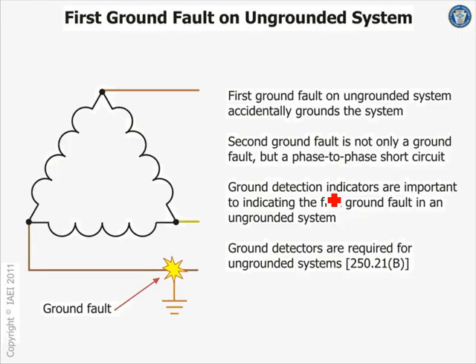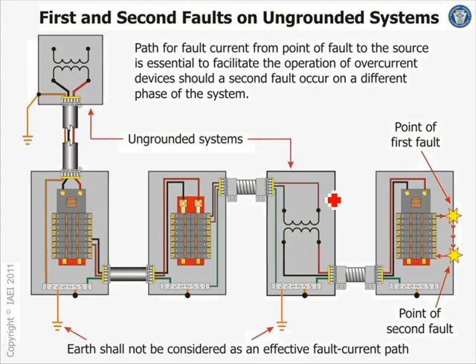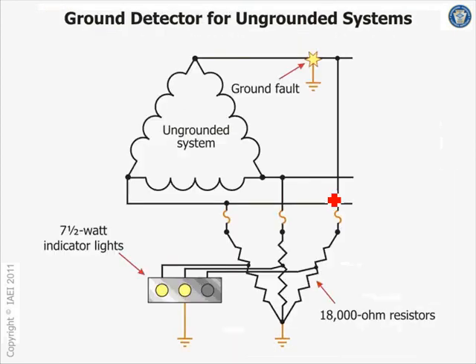Here's a ground fault. The first phase is okay. The second phase will create havoc for your system. Here's a good example of a simple way of detecting a ground, the ground detector required by code for our system. It could be as simple as three lamps with a resistor. This is a voltage balancer to balance the voltage so you don't burn these. And they're tied to each phase.